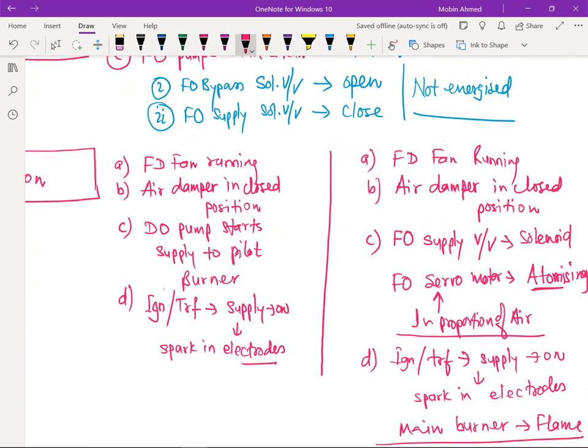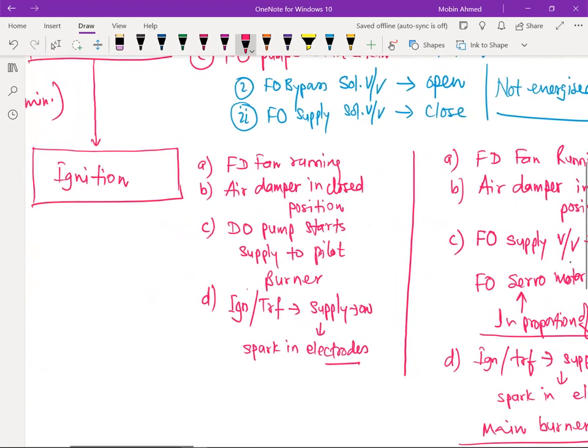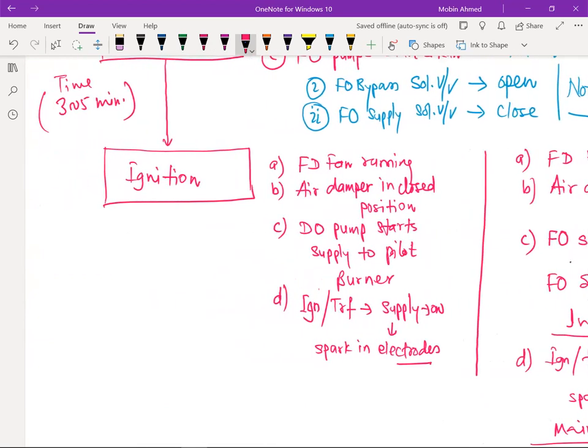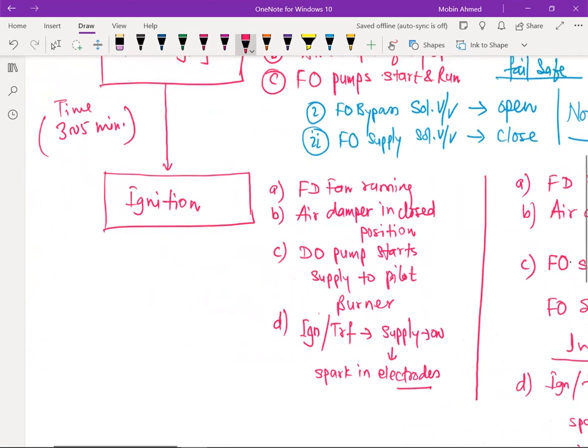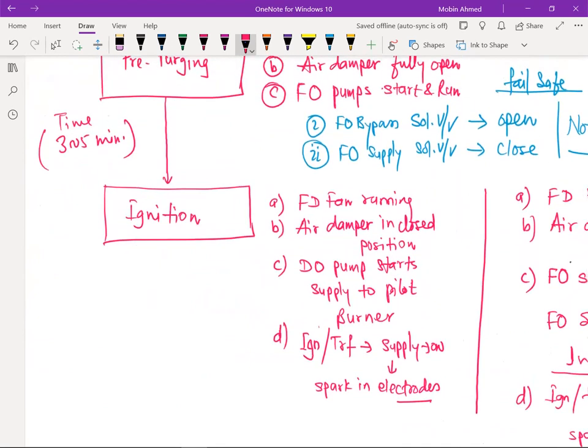But these dampers are in closed position when burning. Sorry? The damper should be closed when the boiler started burning. No, during ignition, not burning. So the air damper should be in the closed position. DO pump, in case of pilot burner, is going to start ignition. Ignition electrode will be there in the pilot burner. This electrode will be there in the pilot burner. So this spark will be there in your electrode.